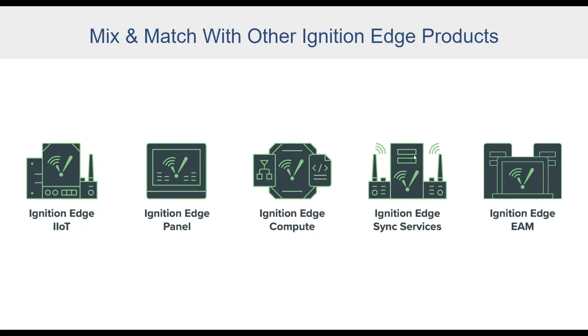The first option is Ignition Edge Sync Services, which allows you to make a gateway network connection up to your central Ignition gateway. The gateway network is Ignition's proprietary ignition-to-ignition protocol, and it will send real-time information, alarm information, and historical data up to that centralized system. If you lose the connection, it buffers data locally and forwards it to backfill your historian once the connection is restored — really powerful in regulated industries where you can't lose data.